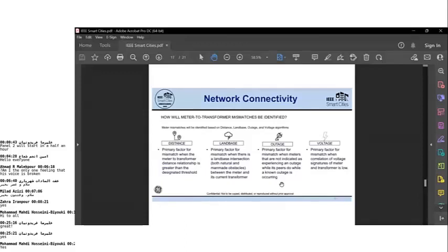The other one is land-based. Basically, electric connections in low voltage distribution systems are designed in such a way as to avoid land-based features, either natural or man-made obstacles like railroads, waterways, highways, bridges. You won't see a line connecting a meter to a transformer over these obstacles.